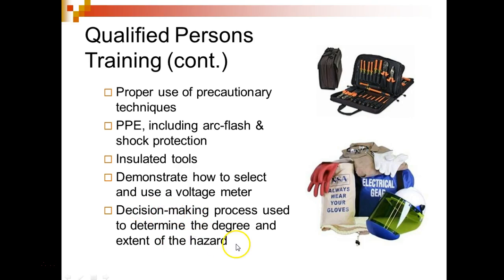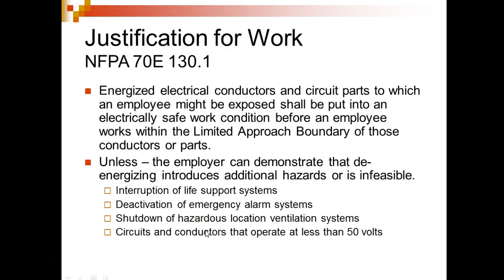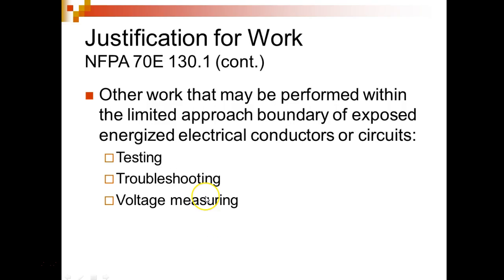Decision-making process used to determine degrees and extent of hazards. The 70E, section 130.1, deals with energized electrical conductors and circuit parts to which an employee might be exposed. They shall be put into an electrically safe work condition before an employee works within the limited approach boundary of these conductors and parts, unless the employer can demonstrate that doing so introduces additional hazards or is infeasible. Examples include interruption of life support systems, deactivation of emergency alarm systems, shutdown of hazardous location ventilation systems, and circuits and conductors that operate at less than 50 volts.